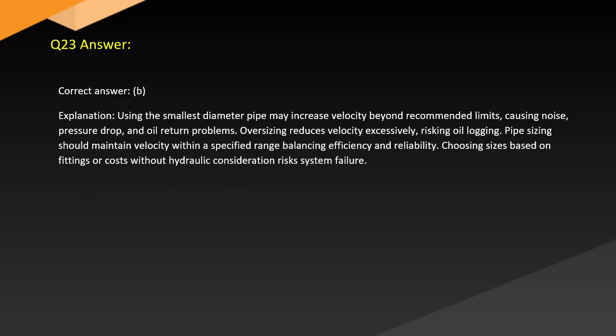Answer. Correct answer: B. Explanation. Using the smallest diameter pipe may increase velocity beyond recommended limits, causing noise, pressure drop, and oil return problems. Oversizing reduces velocity excessively, risking oil logging. Pipe sizing should maintain velocity within a specified range, balancing efficiency and reliability. Choosing sizes based on fittings or costs without hydraulic consideration risks system failure.